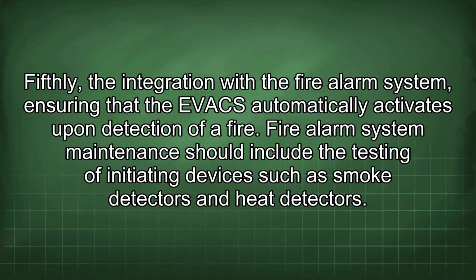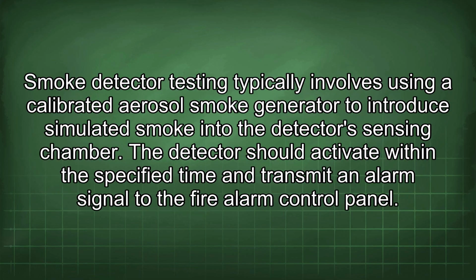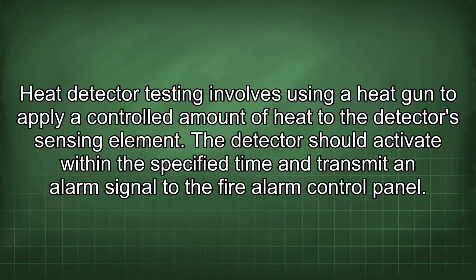Fire alarm system maintenance should include the testing of initiating devices such as smoke detectors and heat detectors. Smoke detector testing typically involves using a calibrated aerosol smoke generator to introduce simulated smoke into the detector's sensing chamber. The detector should activate within the specified time and transmit an alarm signal to the fire alarm control panel. Heat detector testing involves using a heat gun to apply a controlled amount of heat to the detector's sensing element. The detector should activate within the specified time and transmit an alarm signal to the fire alarm control panel.